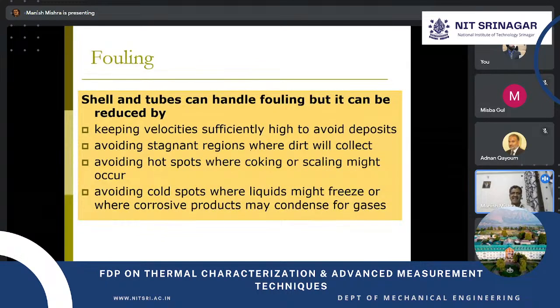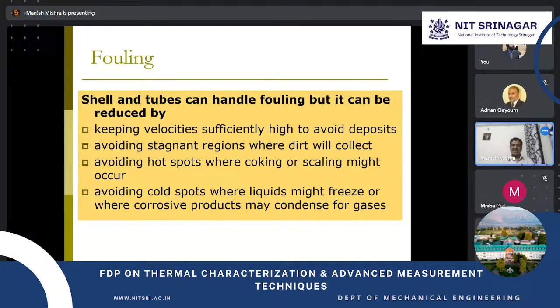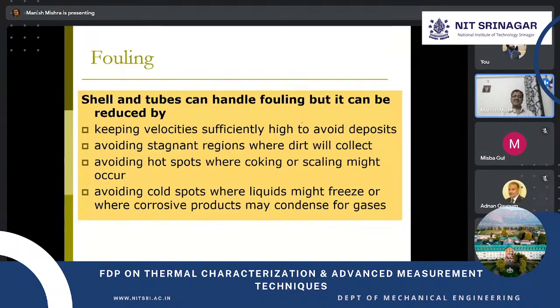Fouling. Fouling is another major issue. Of course, when fouling occurs depends upon the type of fluid we are using. But whatever good quality fluid we use, even filtered, with time there will definitely be deposits. How to overcome that? One requirement is sufficient velocity. If the velocity can be of the order of 1 meter per second, it definitely avoids the majority of the fouling problems.